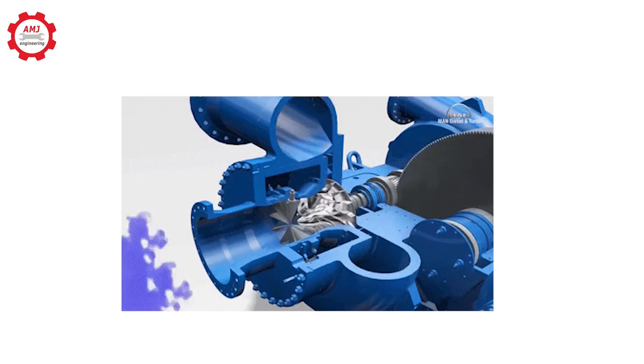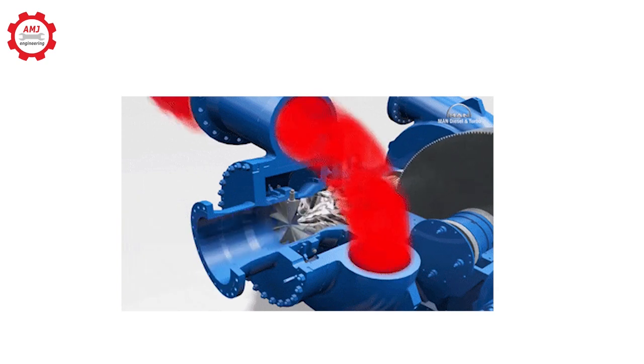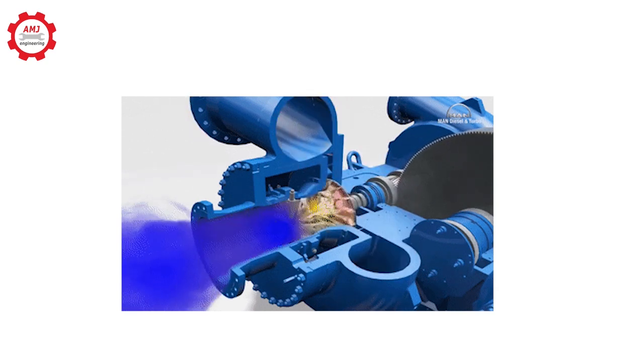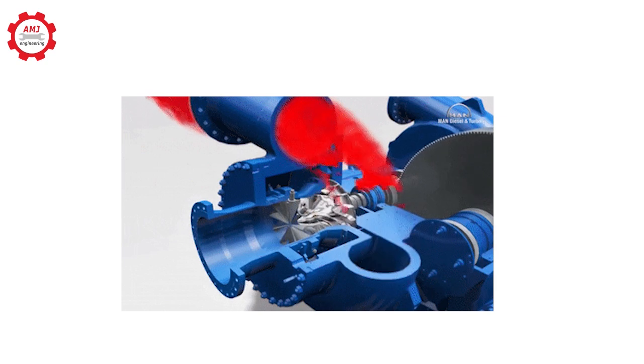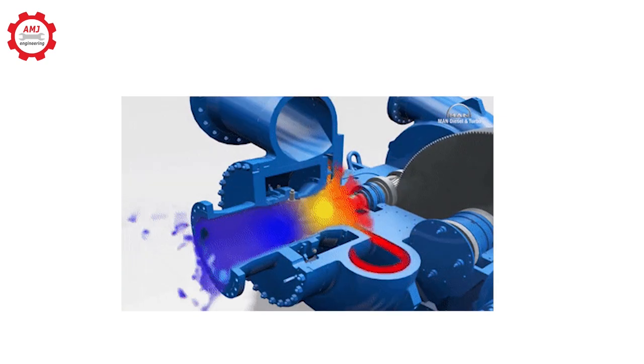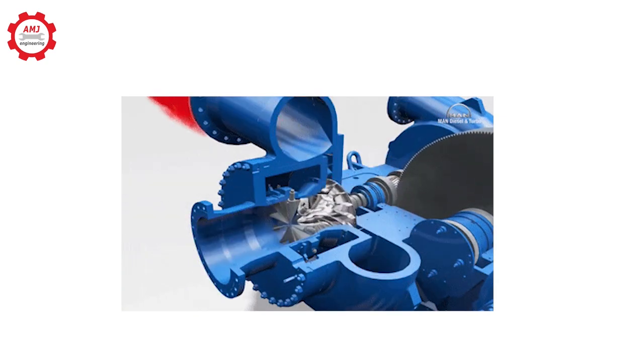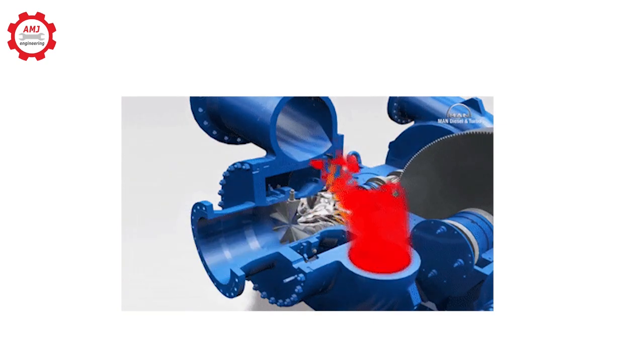Like centrifugal pumps, an impeller provides the force to compress the refrigerant vapor. The low-pressure refrigerant vapor enters the eye of the impeller. The rotating impeller adds kinetic energy to the flow, which is then converted to an increase in pressure by slowing the flow through a diffuser.